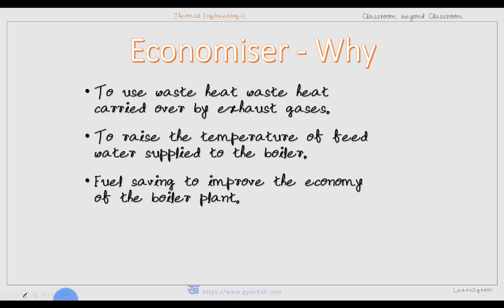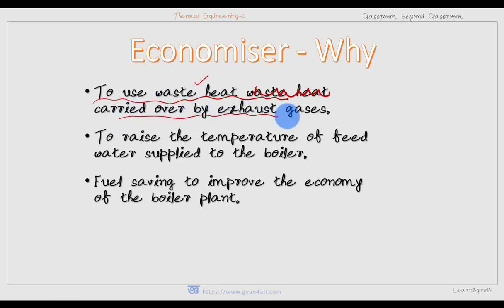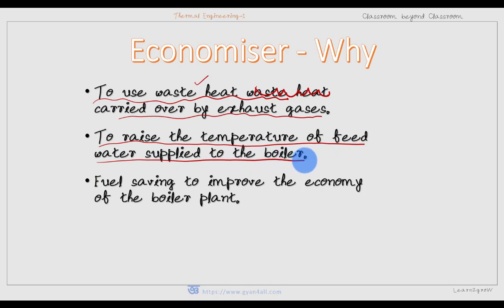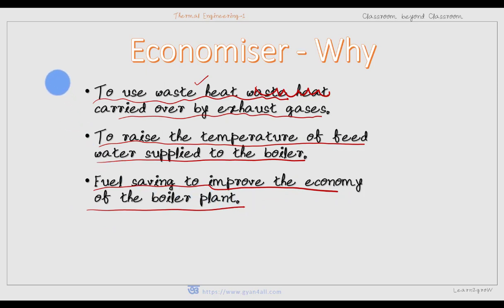The question is: why is an economizer required, or why is it important? First, it is used to utilize the waste heat carried over by exhaust gases, and also to raise the temperature of the feed water supplied to the boiler. This results in fuel saving, improving the economy of the boiler plant. So three purposes are served by an economizer: waste heat utilization, increased feed water temperature, and fuel economy.